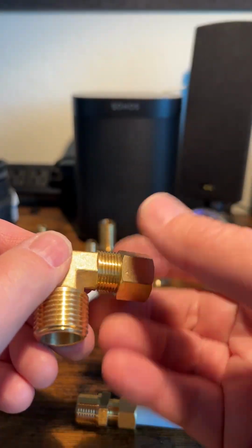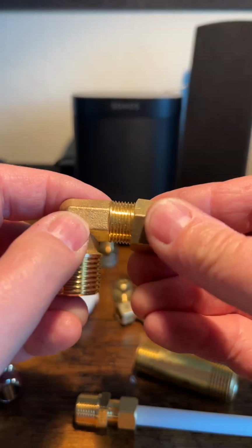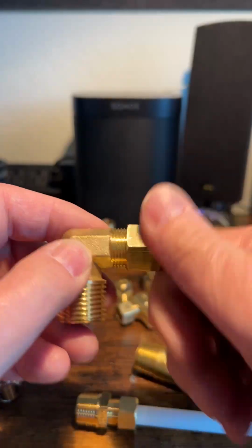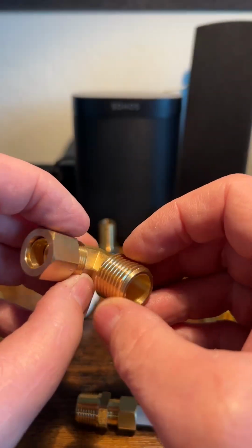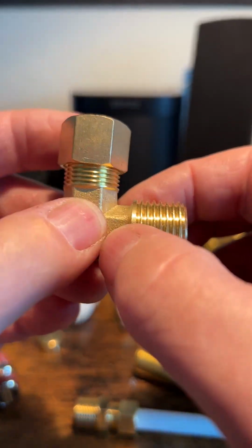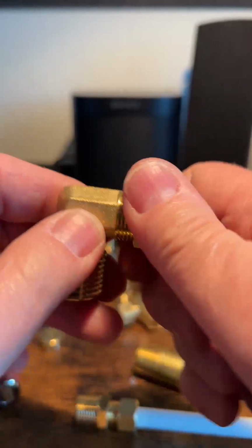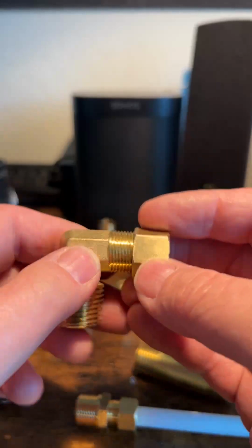So, anyways, compression. Here's another size. They just get bigger and bigger, but you can see how short the shoulder is here? So they're expecting to make that seal in this small amount of space, okay? Where this is a pipe thread, this is a 1/2-inch size, and you can see how deep these threads are. So this would have to screw in really deep with some sealant. This will require no sealant because it's going to use that compression ferrule that's inside to make the seal. And you see that stop at the bottom there, right?